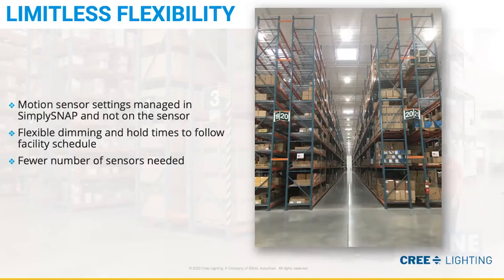Another problem is that the sensor is connected to every light, which adds additional cost. So you have to have a sensor per light, and it results in that popcorn effect. So each light is individually responding to occupancy and vacancy events. In SimplySNAP, a motion sensor is just a device on the network, regardless of which light it's connected to. Motion sensors can control any number of lights in the zone, regardless of the location.